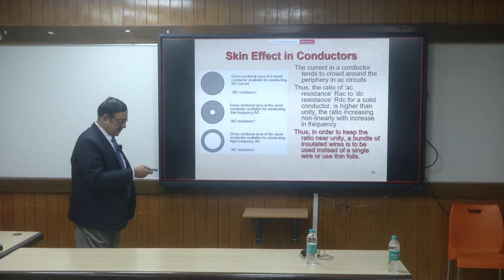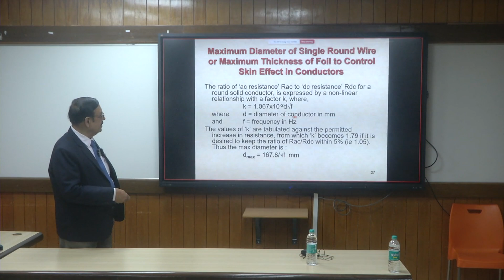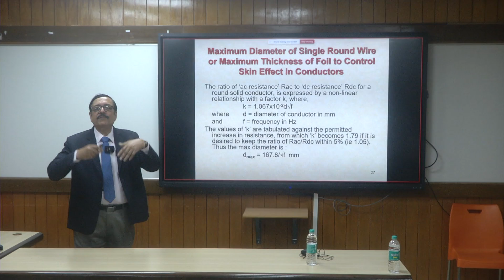It shows that skin effect is definitely dependent on diameter. You can get this data from textbooks. And if you want to keep AC resistance by DC resistance within 5%, that is a 1.05 value, you have to stick to this formula, where in the denominator root F is the frequency in hertz. That tells you what is the maximum diameter permissible for one conductor. Now you go in for multiple conductors to create the current carrying capability of the winding.